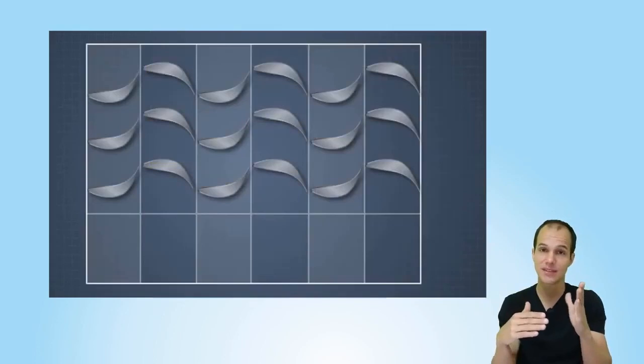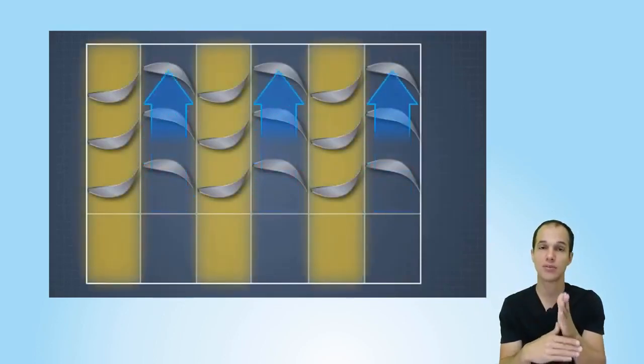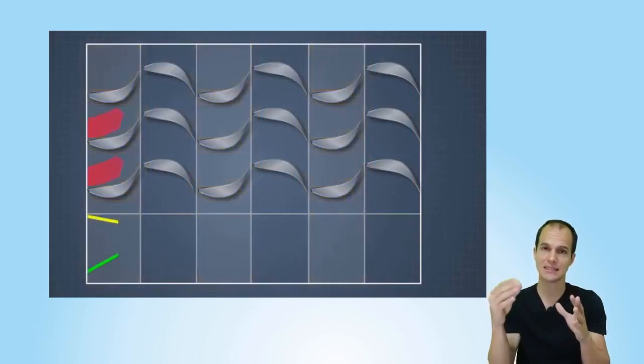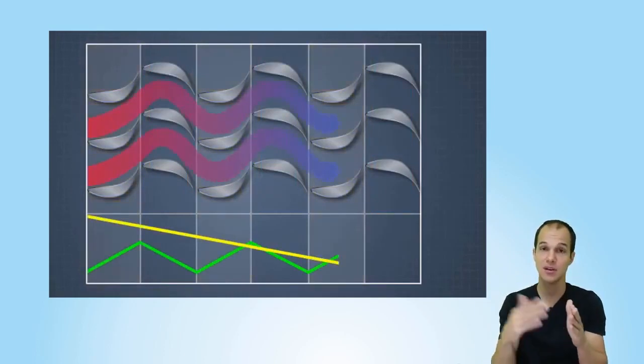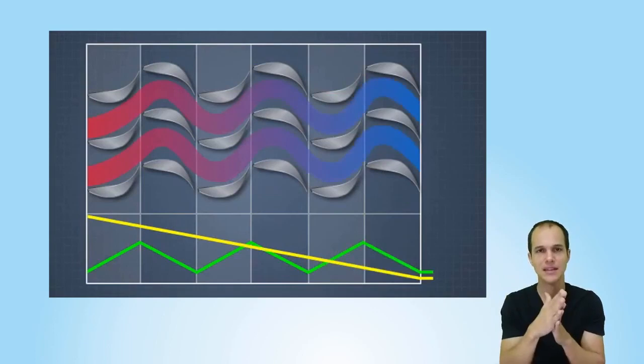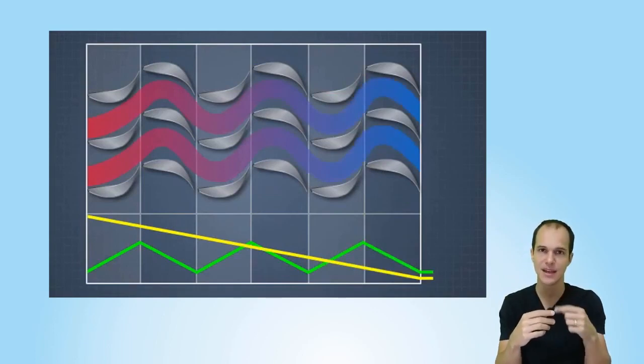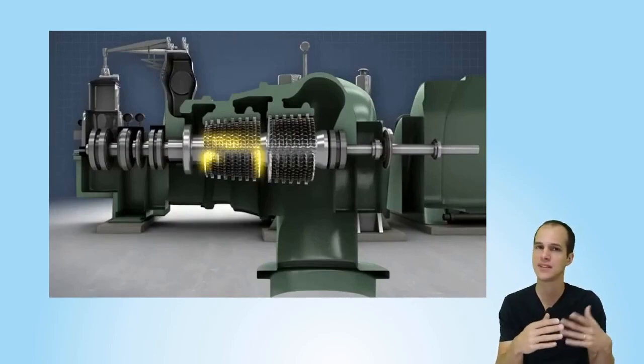At this moment we have another wheel mounted in the sequence. It will capture this velocity, this fluid that we are directing. With this increase in speed that it had, it will capture it and pass through the vane. It will convert it into kinetic energy and mechanical energy. At that moment again, we will have one more drop in pressure and temperature, and so the process will be repeated for as many stages as there are in the rotor.